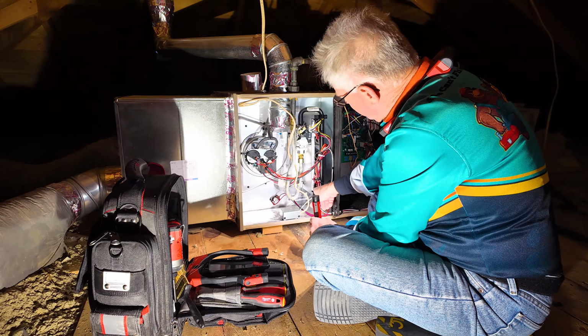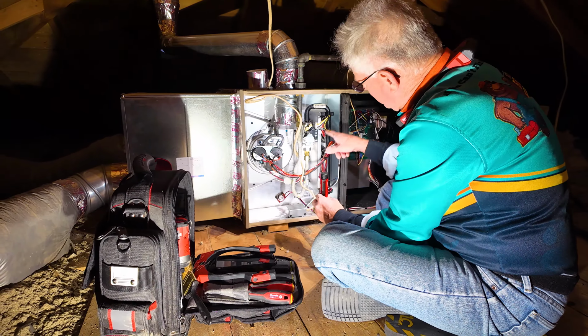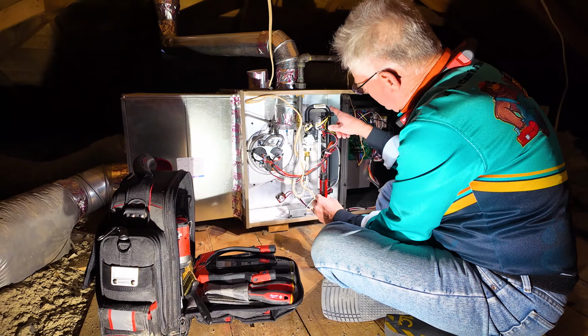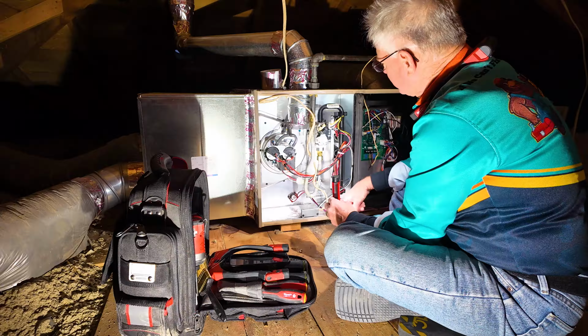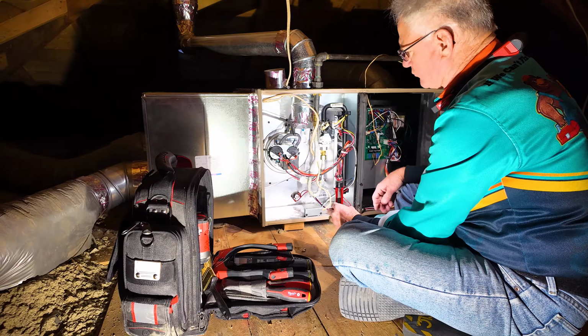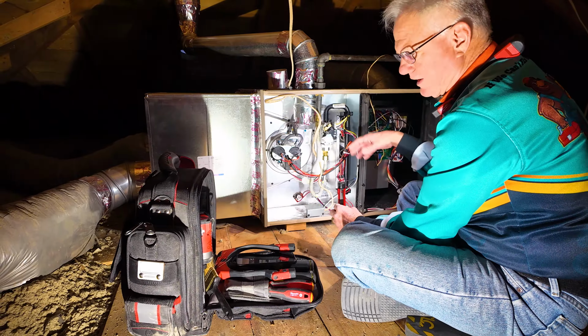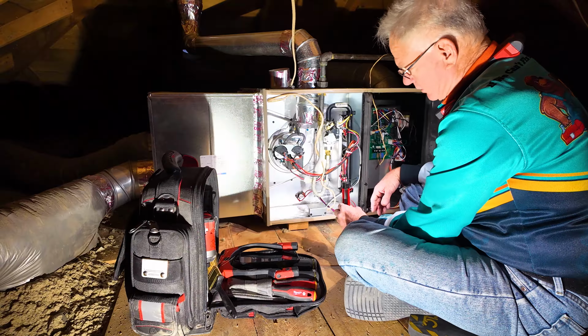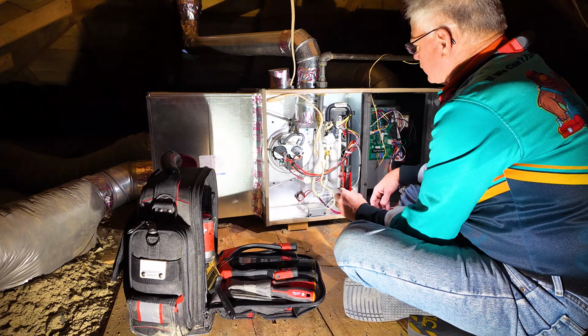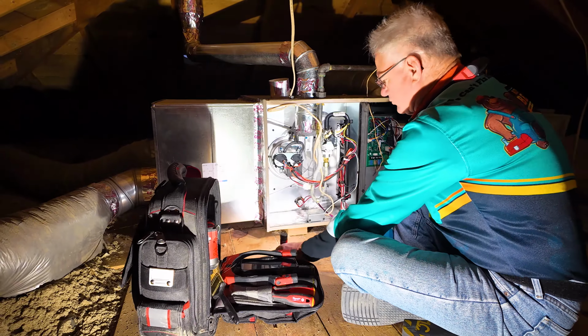If for some reason this one doesn't light down here, it doesn't get all the way across, then it will not heat up that rectifying flame sensor rod. If it doesn't heat that up, then it shuts the gas off, because it doesn't want the gas to run without all the burners burning. Safety again. So that's my suspicion, that the flame sensor's dirty.